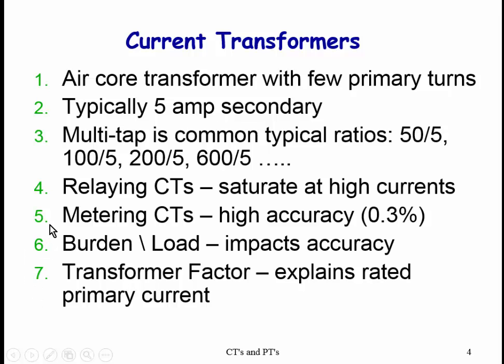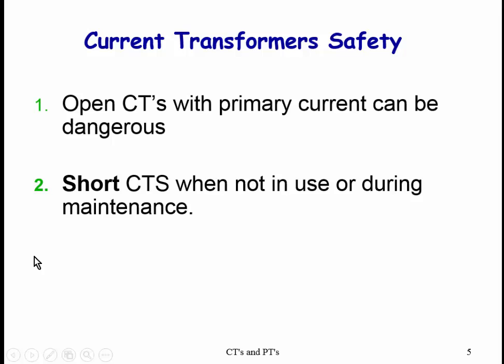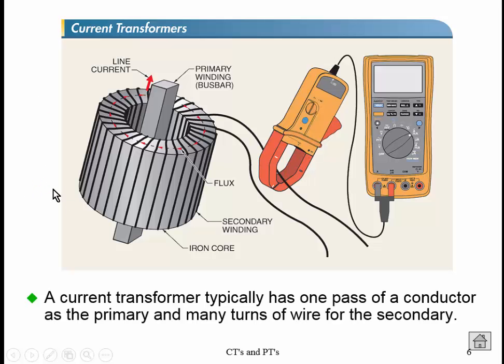Now, these CTs, and you'll see with the PTs, they're really not meant to energize things. Like, they're not really meant to drive loads. They're meant for measurements. So we try to limit how much, when we call it burden, how much equipment we put on these things, because we don't want to impact their accuracy too much. So one of the key things to remember with CTs is that an open CT can be dangerous. A shorted CT is a safe CT. And that is just the opposite of what we're used to compared to voltage transformers.